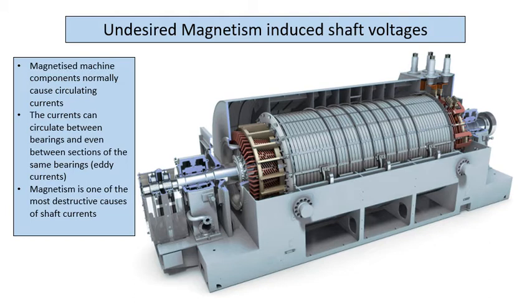Often, and someone mentioned this earlier, if you've got a voltage from end to end, and you put brushes there and there, what's going to happen? You're going to give the current a path to flow, and if it's a high current, your brushes will last a couple of weeks. So ideally, you want to find one point to earth, and then you can see here they actually monitor the voltage. And this is from MPS, Magnetic Products and Services. They came up with the whole concept of using shaft voltage and current as a monitoring tool, because your shaft voltage generally is related to axial flux. By monitoring your shaft voltage and looking at the different characteristics, you can monitor your plants.